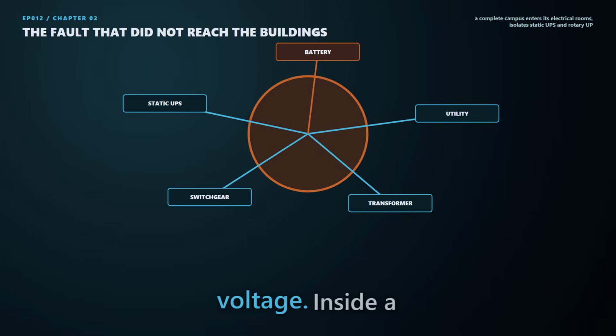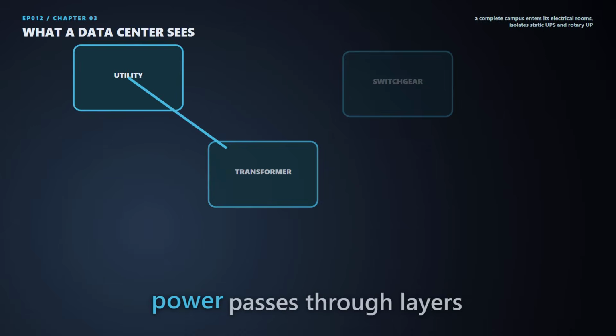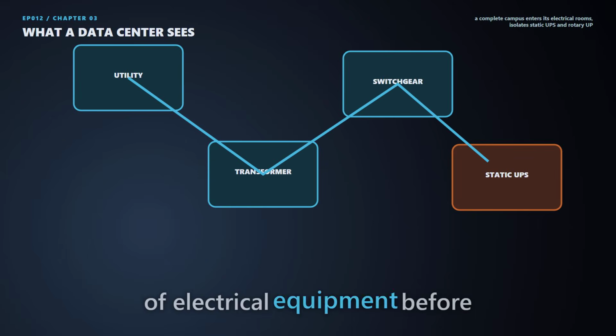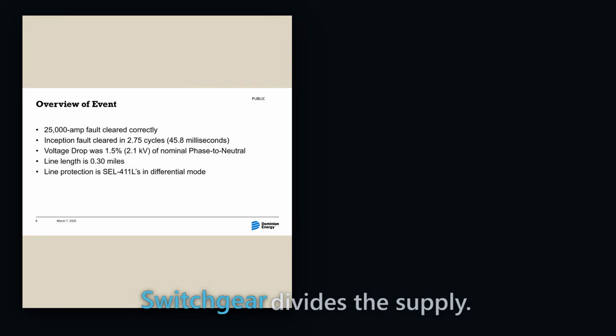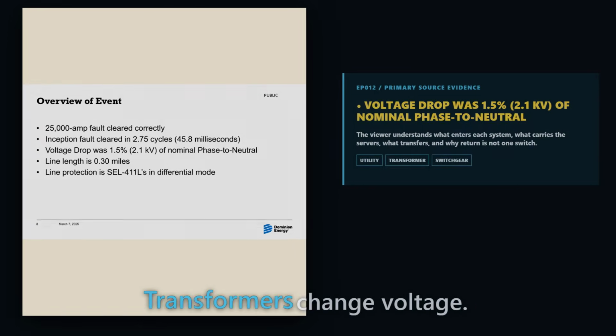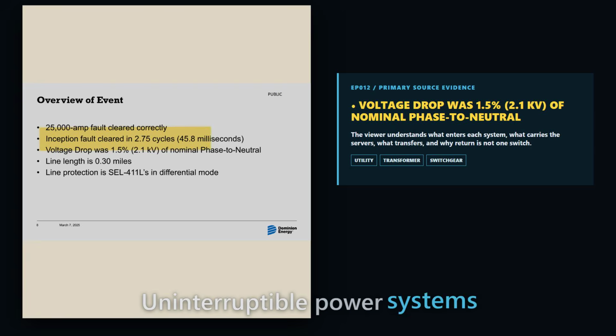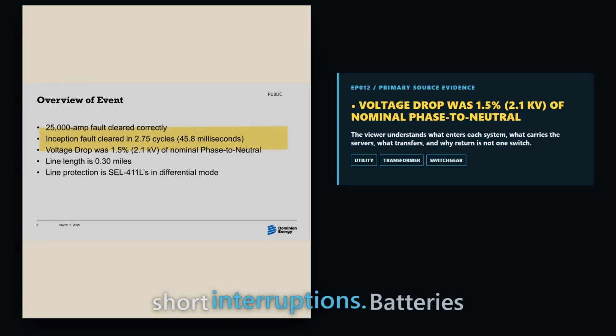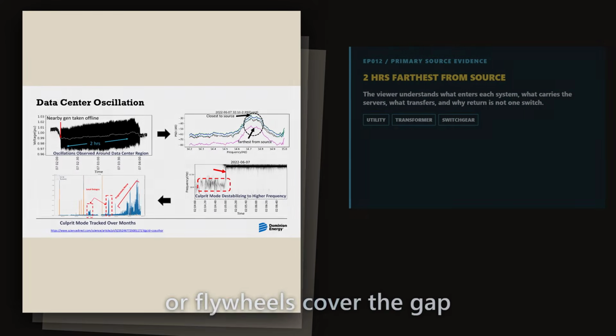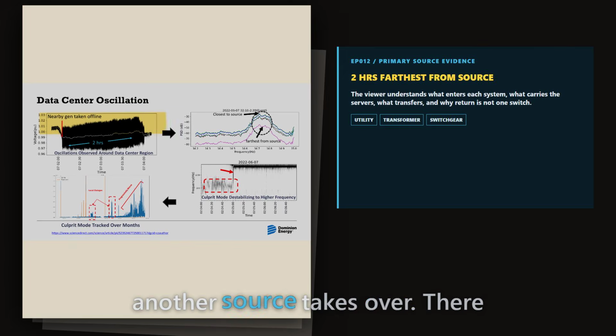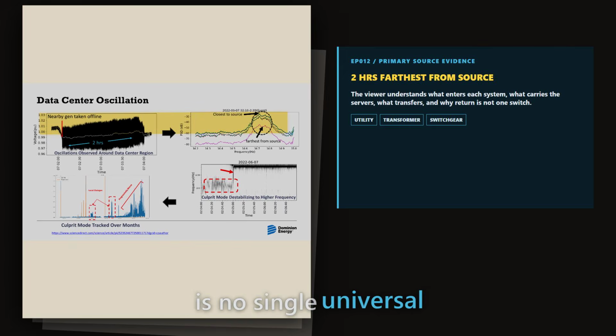It experiences voltage. Inside a data center, utility power passes through layers of electrical equipment before it reaches computing hardware. Switchgear divides the supply. Transformers change voltage. Uninterruptible power systems condition the power and bridge short interruptions. Batteries or flywheels cover the gap while generators start or another source takes over. There is no single universal design.